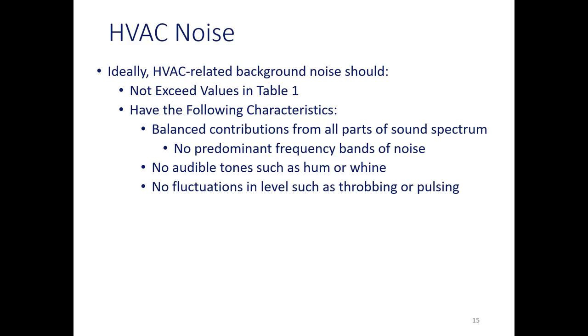But beyond matching that number in the table, we want it to have the following characteristics. So we want balanced contributions from all parts of the sound spectrum, meaning low, medium, and high frequencies, in proportion. It's fairly similar to A weighting, just that more low frequency sound is acceptable because we're less sensitive to it. And fortunately, that is the louder, harder sound to deal with from MEP systems. And then as we move up to mid and high frequencies, we need reduced levels. It follows that same curve. Then no predominant frequency bands of noise. So we don't want anything tonal. And then we say that again in this next one.